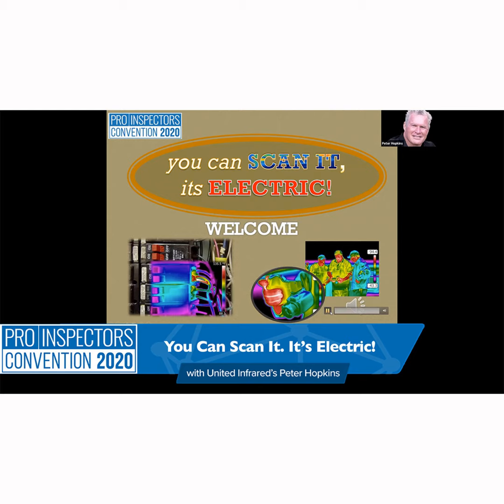So there are opportunities, but these are things that you'll run into, and you need to know how to walk the walk, talk the talk. You might sometimes see on electrical switchgear where they put a window in - those are viewing ports, but infrared does not transmit through glass or plastic. You have to use specialized material, typically a crystal or polymer, depending on the kind of window it is.